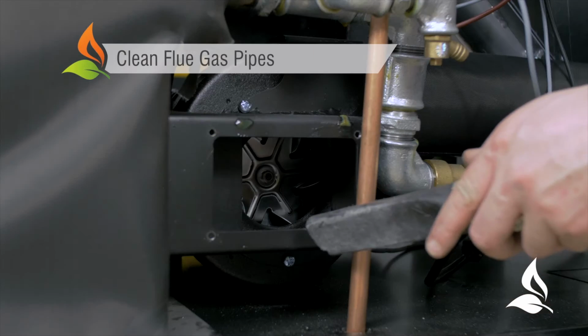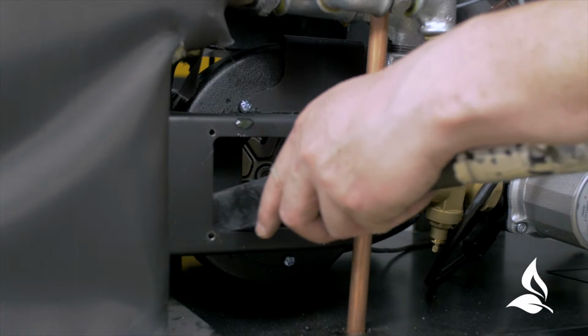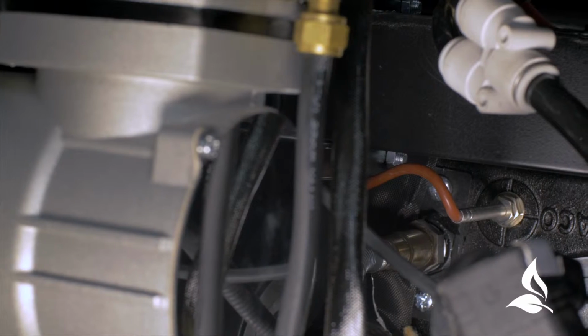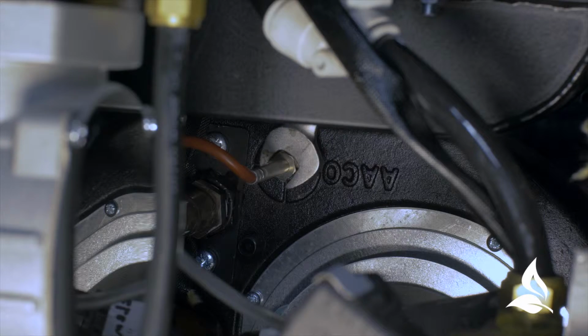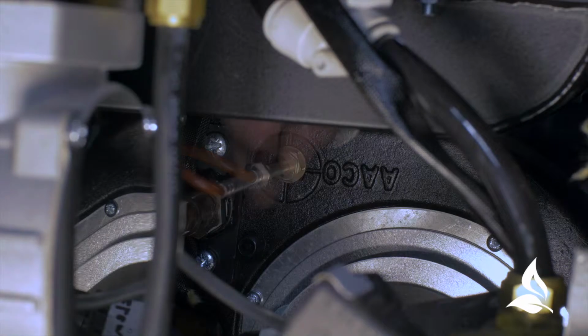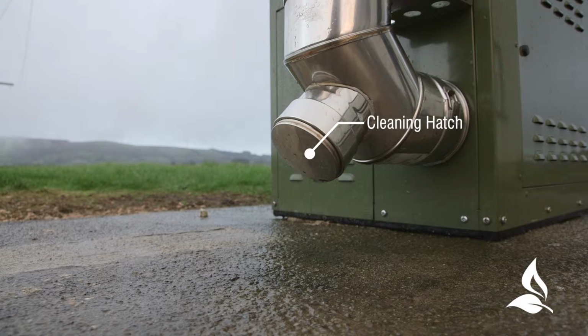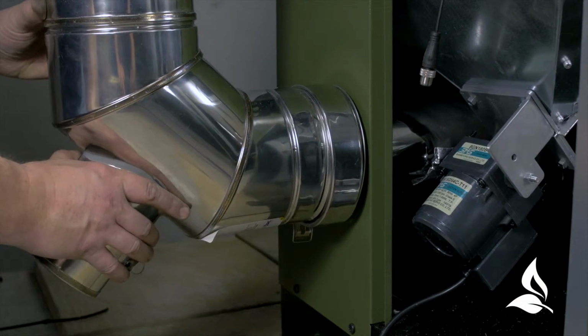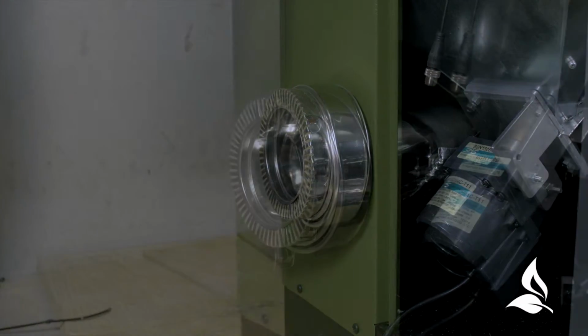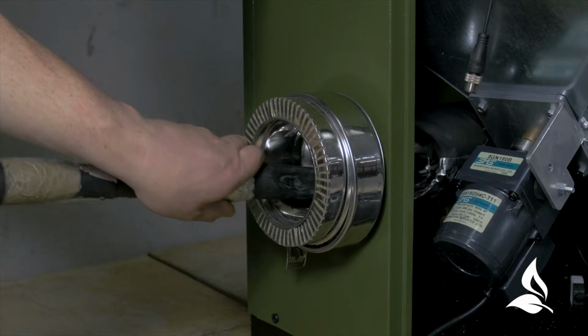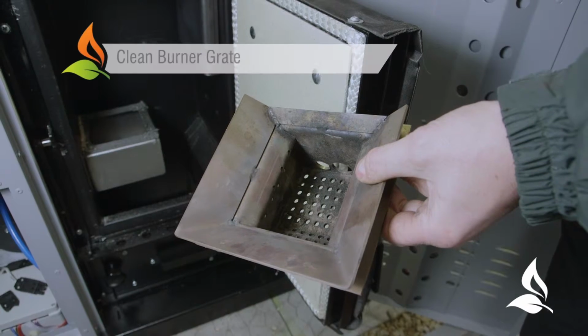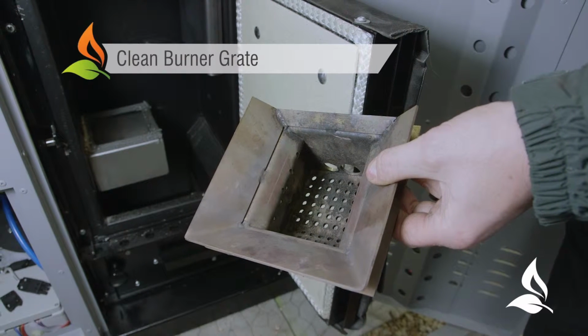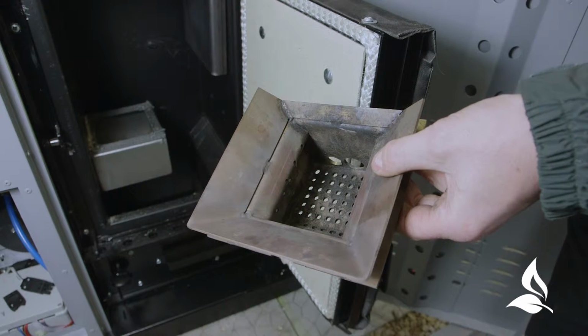Remove the exhaust fan access plate and clean the flue gas passageways to the flue outlet. Remove and clean the flue gas thermocouple. Completely clean the flue through the inspection door and also remove the flue. Remove the burner grate and remove any loose ash in the grate holder. Ensure all the air holes in the burner grate are clear.